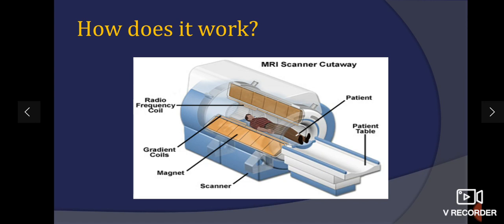So the major components of the MRI scanner are the main magnet, which polarizes the sample. Okay, the gradient coils for correcting the shifts and the homogeneity of the main magnetic field. So this gradient system is used to localize the MR signal, and the RF system which excites the sample and detects the resulting NMR signal. The whole system is controlled by one or more computers.